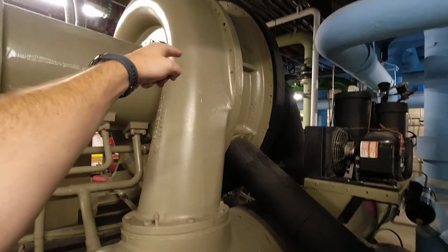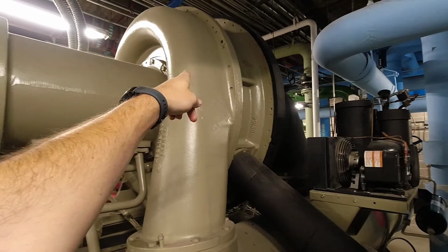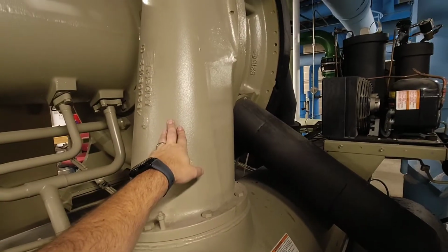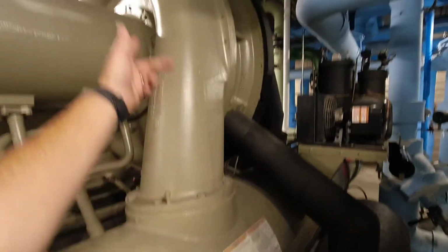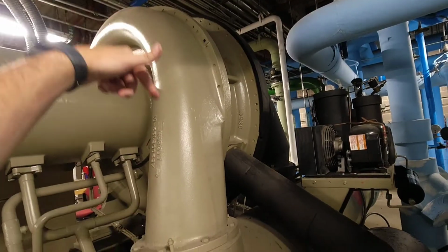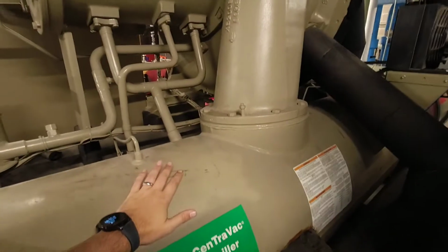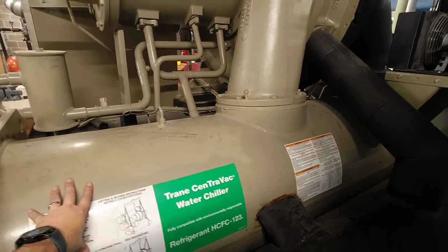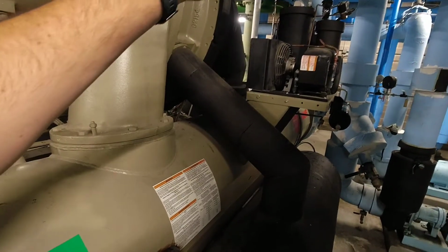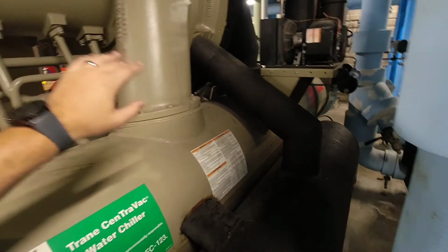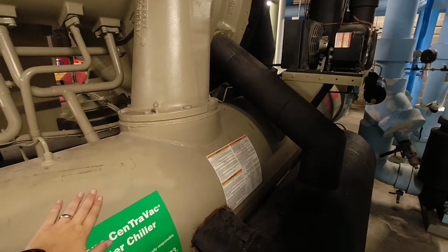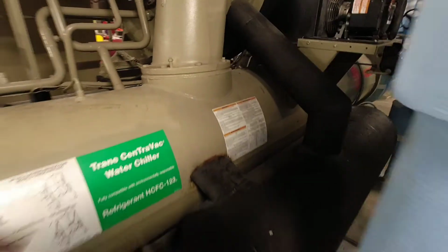So we go through the suction, through the impellers, and then we come into the volute and out of the scroll. So this is called the scroll or the volute, and it comes down into the condenser. From the condenser, water is going to remove the heat and send it out to the cooling towers or however you decide to utilize it, and it's going to function as a standard condenser at that point. Coming out of the condenser, you've got your liquid line, which is right here. So your liquid line comes out.